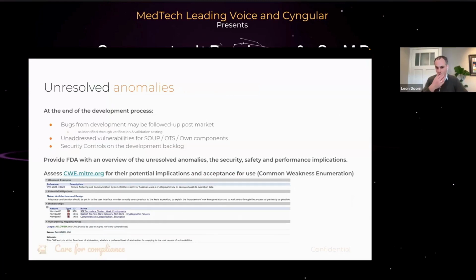One way to do that, suggested by the FDA, is to look at the Common Weakness Enumeration. It's a public database, also published on MITRE, and you can just search. It gives you a very good option to scroll to certain items and see if your type of vulnerability or your type of anomaly is listed and what type of security risk is associated with it. It will also give you an idea of whether you should be using that in your device, yes or no, and under what conditions. In this case, you see that the one in the example below is acceptable, but there's also a bunch that are unacceptable, for example, for having those available in your device. And this is specifically related to known medical device issues. So it's a good database to have a look at.